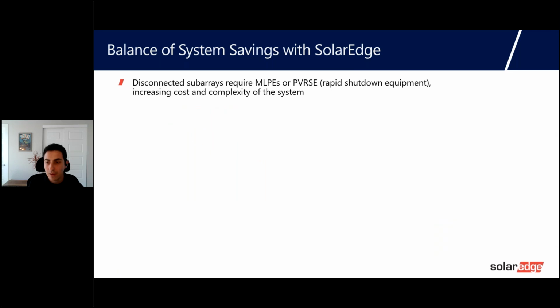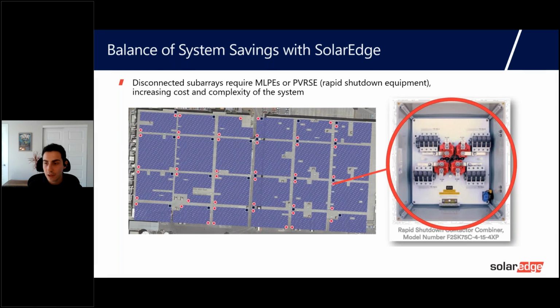And finally, the other piece that we're seeing consistently have an effect here is the requirement of MLPEs or PV rapid shutdown equipment to maintain NEC compliance. It is sometimes possible to avoid the use of these devices entirely, but it is quite rare to have a C&I rooftop without some breaks in the array, given the necessity for fire code walkways, rooftop obstructions, and other reasons that rooftops aren't perfect for us when we're designing systems.